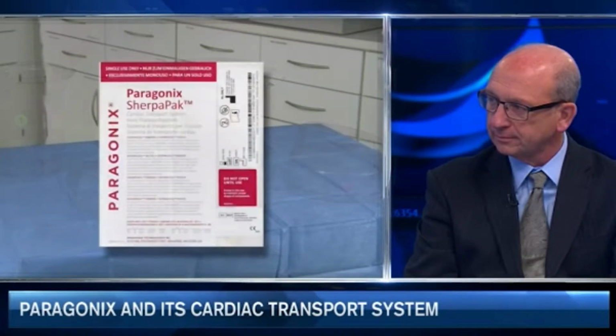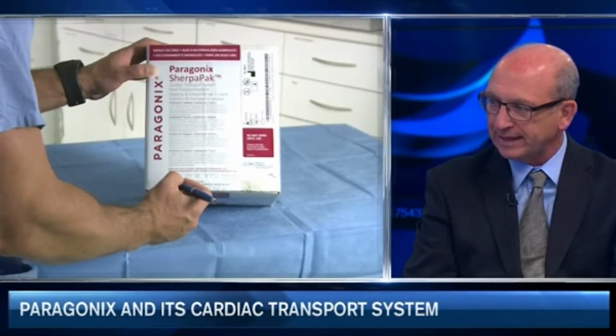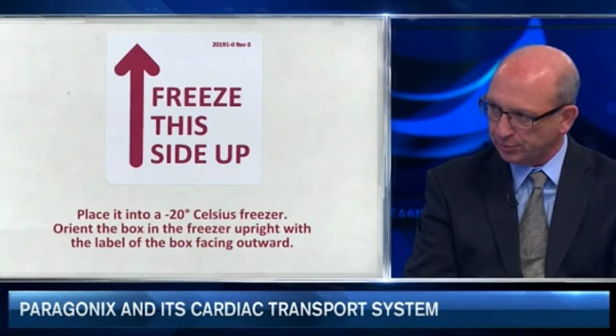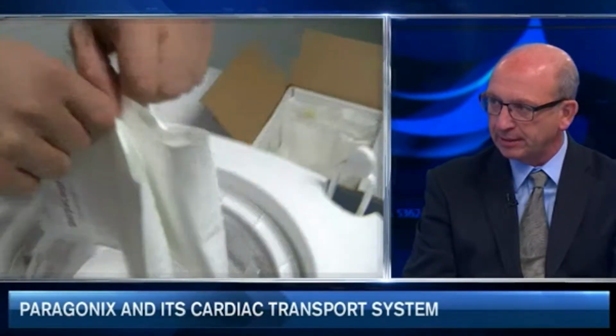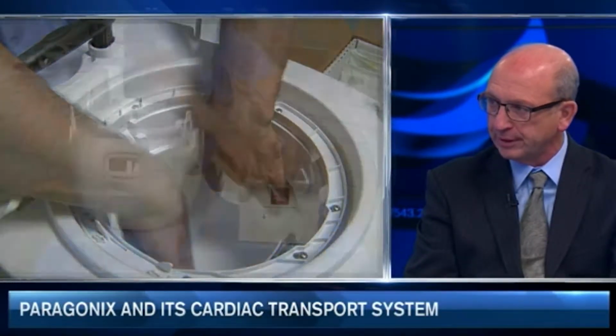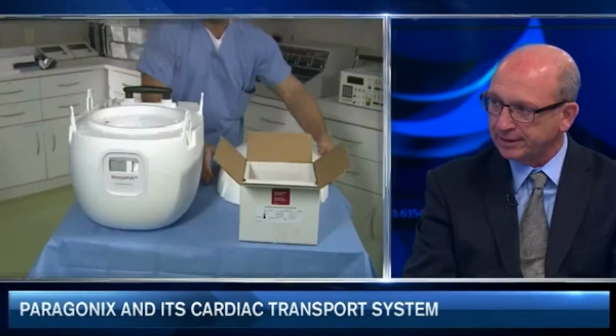And that helps to promote the viability of the tissue of the heart as it's being transported from a donor to a recipient. So in the past, when you're essentially packing it in ice, are you doing damage to the organ? Well, in several ways you can be. The temperature of ice is 0, and the tissue of the heart is almost in direct contact with the ice. It's being sandwiched between heavy layers of ice. And when that happens, it deforms the organ and can also freeze the organ. So you can end up with frostbite and frozen regions of the heart. And the reaction is that upon implantation and resuscitation, that heart may not perform in an appropriate way.